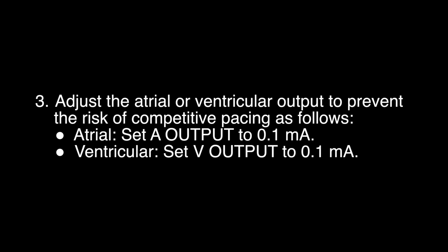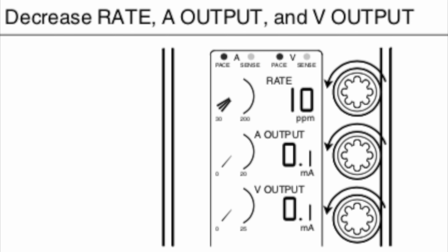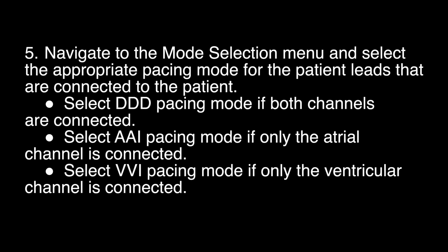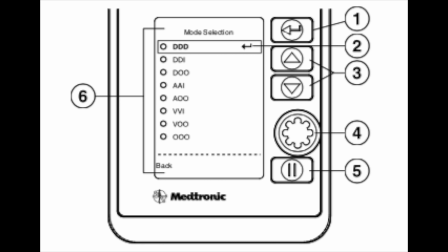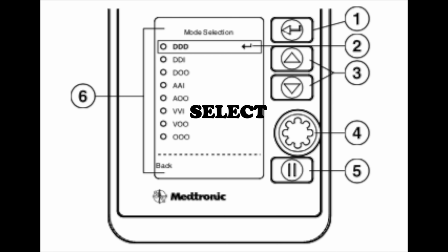3. Adjust the atrial or ventricular output to prevent the risk of competitive pacing as follows. Atrial, set A output to 0.1 mA. Ventricular, set V output to 0.1 mA. Decrease rate, A output, and V output. 4. Connect the temporary pacemaker to the patient lead system. 5. Navigate to the mode selection menu and select the appropriate pacing mode for the patient leads that are connected to the patient. Select DDD pacing mode if both channels are connected. Select AAI pacing mode if only the atrial channel is connected. Select VVI pacing mode if only the ventricular channel is connected.